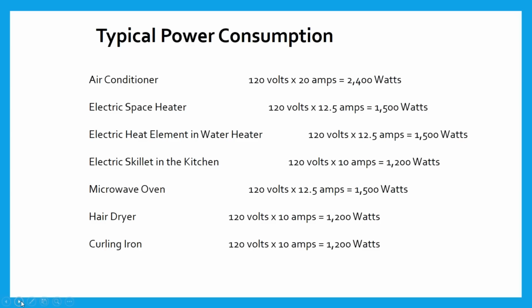Look at the electric space heater. Now this is like the space heater that Mo has. I flipped it over and got to looking at it. It's putting out 1,500 watts. That 1,500 watts is broken down to 120 volts times 12.5 amps. Now let me just tell you, the receptacles that we're plugged into, the circuit breaker for that receptacle is 15 amps. So I mean, we're just right below the threshold.